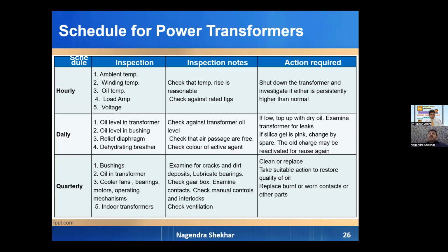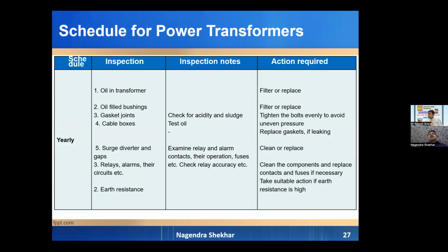Quarterly, once in 3 months: bushings, oil in transformer, cooler fans, working of the fans, any noise, bearings, motors, operating mechanism, thermostats, etc. Yearly inspection: oil in transformer, oil filled bushings, gasket joints, cable boxes and their terminations, surge diverter gaps, relay alarms, their circuits and proper functioning, and earth resistance as well.